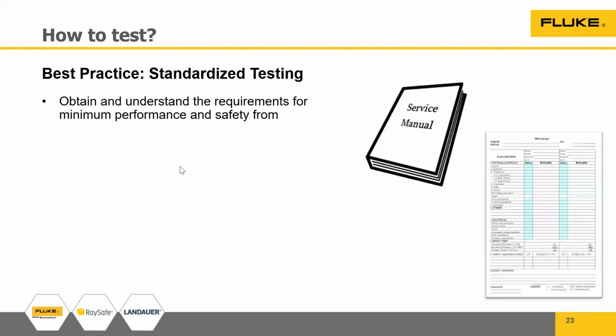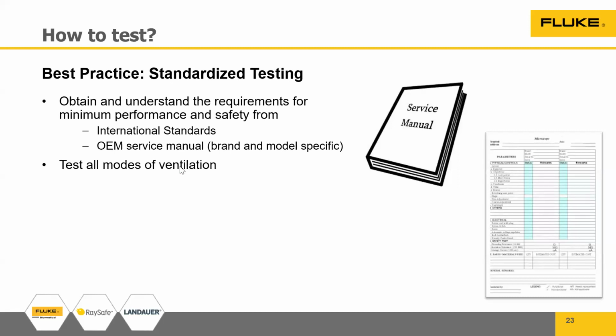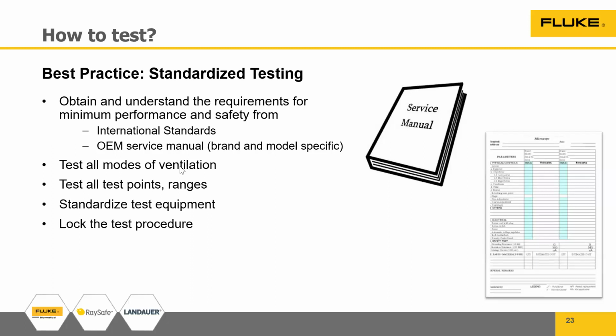It is to obtain standard requirements for minimum performance and safety. So how do you obtain them? One is the international standard. Just now I talked about something from IEC, but apart from that, the OEM guidelines or OEM service manual is the best place where you can get the standardized procedures or bare minimum things one needs to check. Okay. And when it is a ventilator, apart from the electrical safety part, you need to check other parameters also, like ventilation, all modes of ventilation, test all points, all ranges. That is very, very important. Okay. And keep the standardized test procedure, so that next time when you have to do it, you know what procedure you need to follow, and record that procedure. Okay.